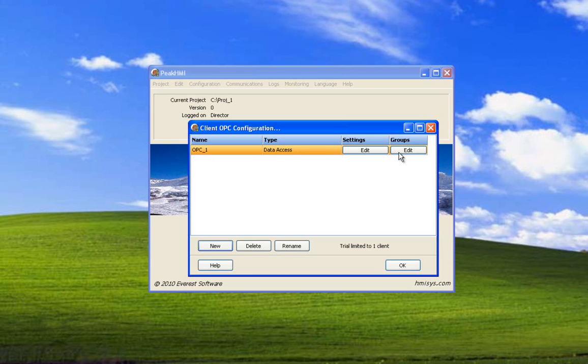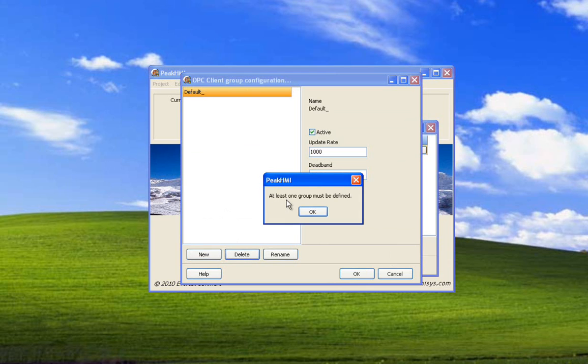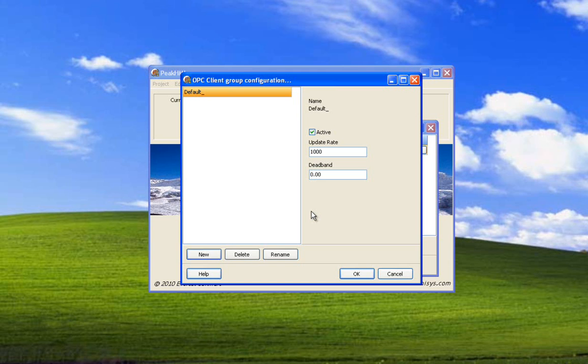And now we're going to select groups. There always has to be at least one group configured. If we try to delete it it will tell us at least one group must be defined. We'll just leave it as default for now. We're going to set the dead band to zero because we know this server won't have any noise coming across the analog values. The dead band will only change when we change it so we don't have to worry about noise. We do want the group to start up as active.